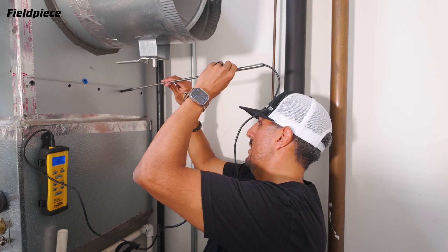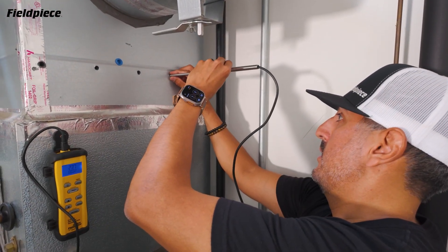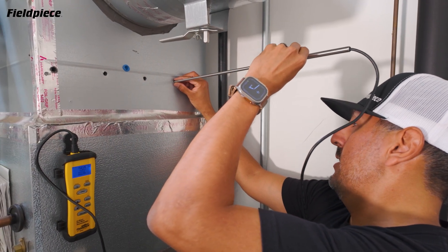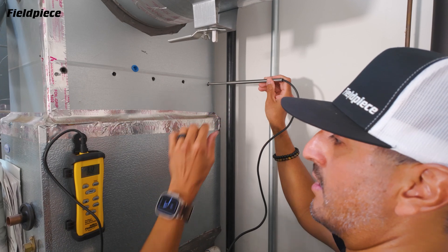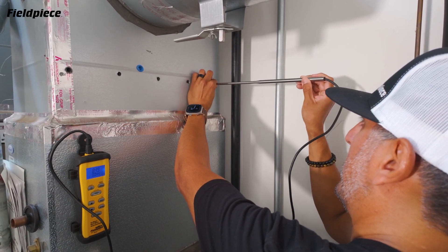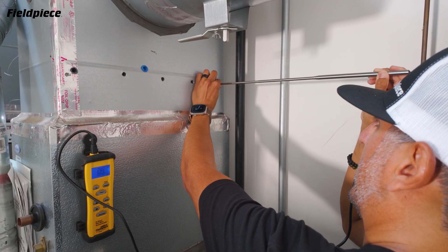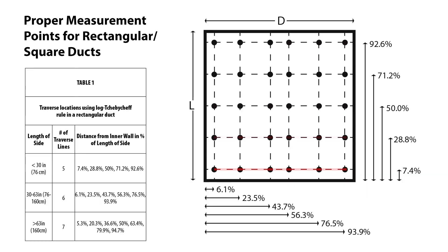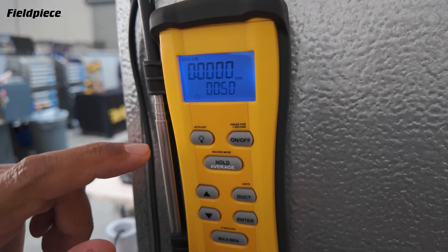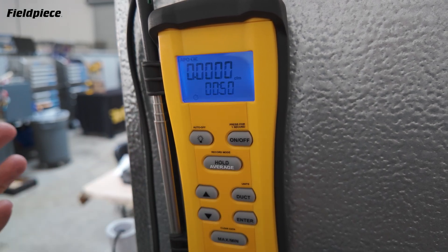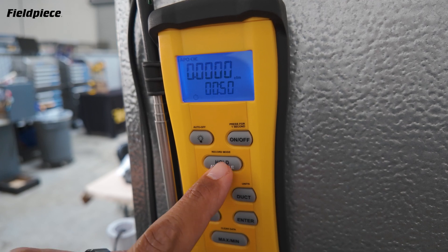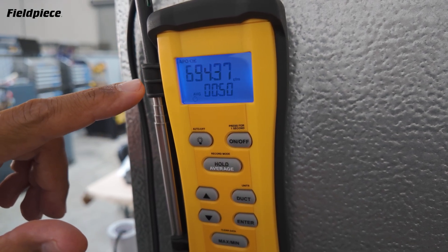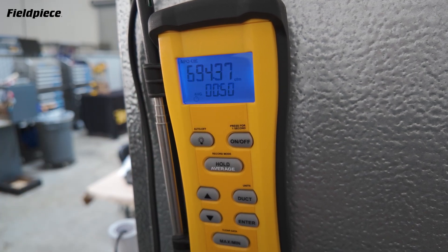I pause, insert into the fourth hole, press enter, and pull it back — the tool is sampling all of the airflow during that time. Then for the last hole I insert it, press enter, uniformly pull it out, and press enter to stop. Once you finish all five legs you've sampled all the measurements needed for the tool to perform the calculation. Back on the display I can see the total test time was 50 seconds — that's good because I had five holes at 10 seconds per hole. I press the average button and it shows my average CFM was 694 CFM, just under 700 CFM.